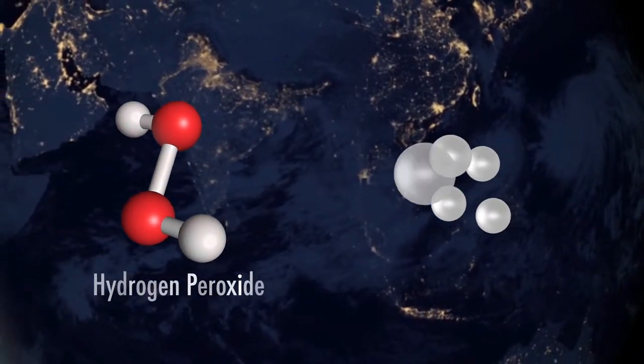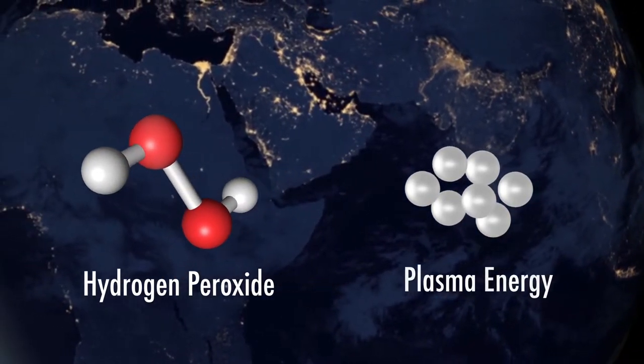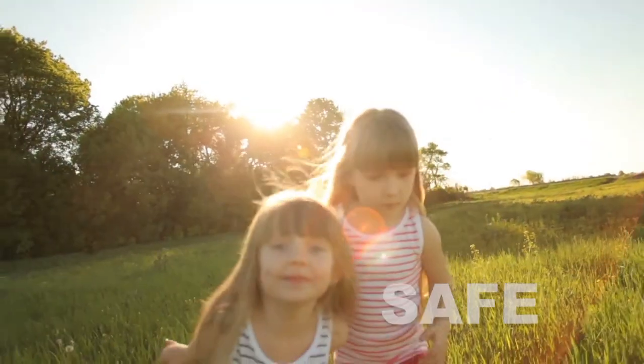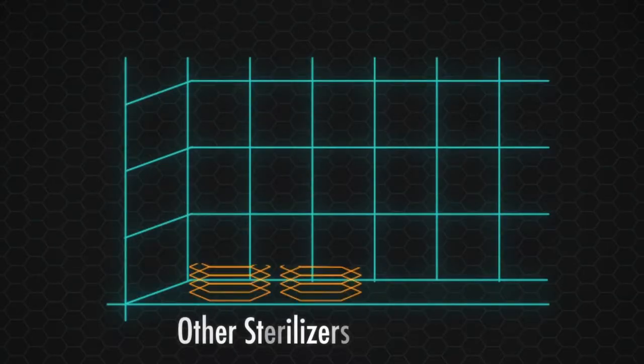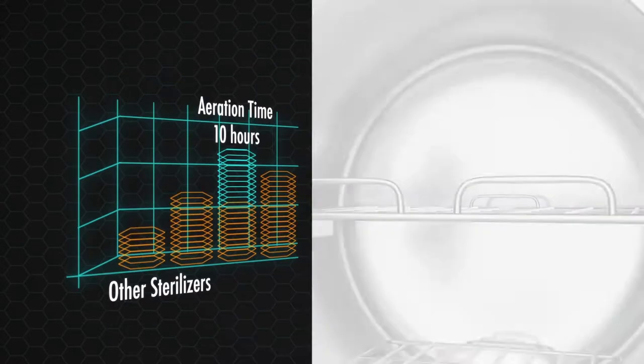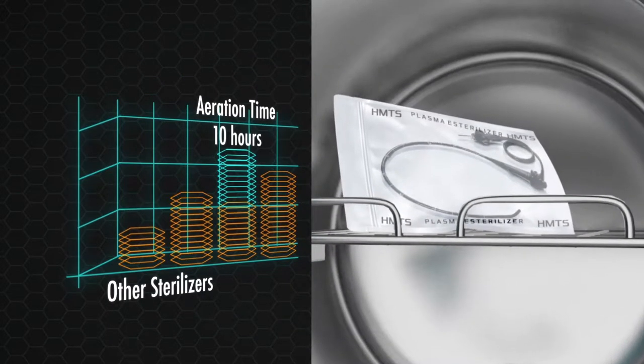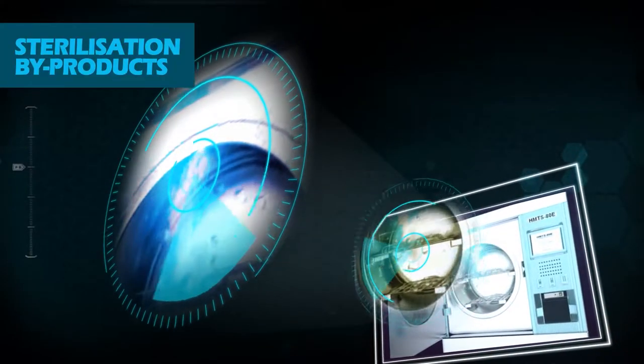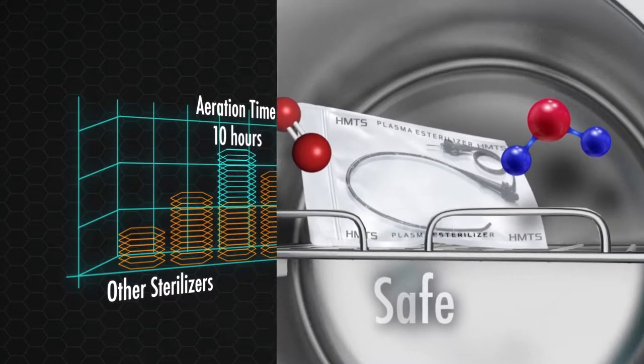The HMTS series meets the strict environmental standards of the world by utilizing the sterilization properties of hydrogen peroxide and plasma energy, which eliminates the problem of exhaust gas. Due to the CFC gas of previous sterilizers, residue toxins would take 10 hours alone to aerate for the protection of users. However, with the HMTS series, the final byproducts are only oxygen and water, making the sterilization process safe and reliable.